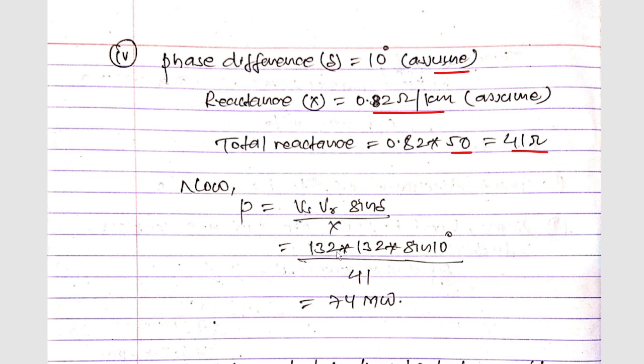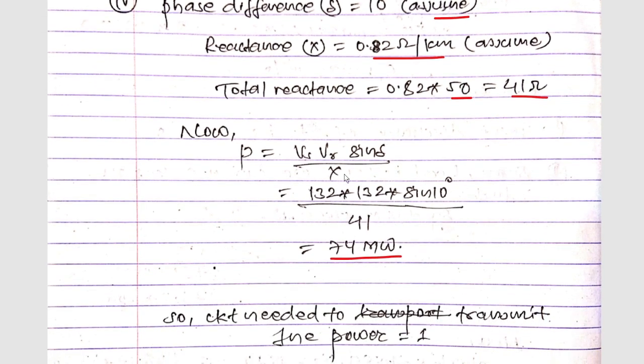Taking sending and receiving voltages as 132 kV: 132 × 132 × sin(10°) / 41. Since this is in kilovolts, the output will be in megawatts. We get P = 74 megawatts.